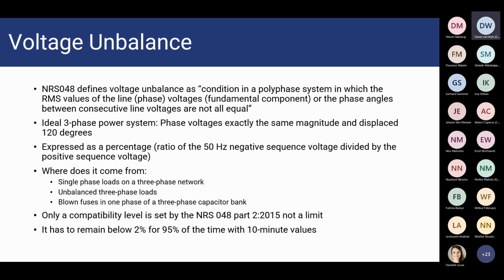Okay. Sorry, Donnie, Randolph here. Just on that, although we focus here on the load, it's purely due to the principle that common things occur commonly. So if you consider the likelihood of it happening on the generation end of things, a voltage unbalance from the generator side is more likely to be picked up by a generator protection system and to be cleared quickly, whereas a load can sustain for a longer period of time.